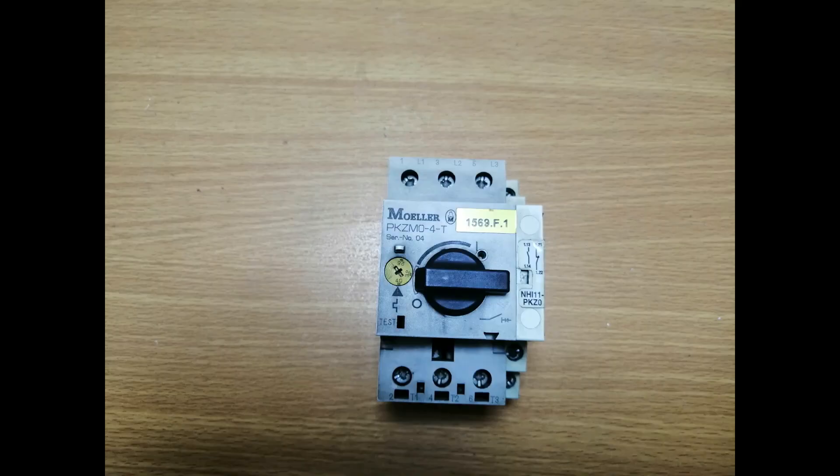Hey guys, Shayan here from Talk Engineers. Today we have a three-phase circuit breaker with us from MOELLER. It's an industrial grade circuit breaker which we scavenged last night from one of our machines — it was causing some signal issues and we believe that its contacts have been carbonized. So we have checked it out for servicing.